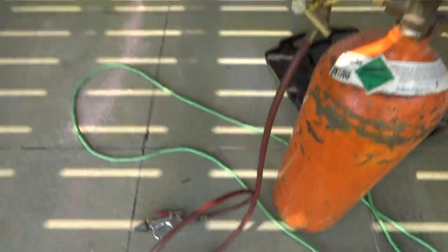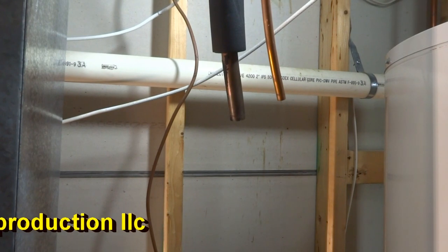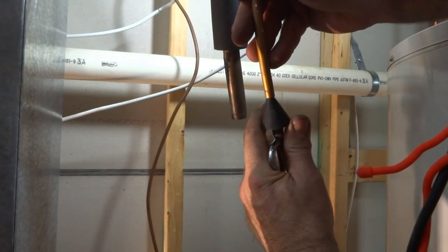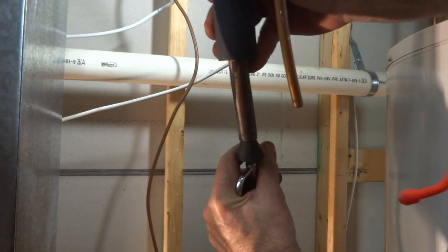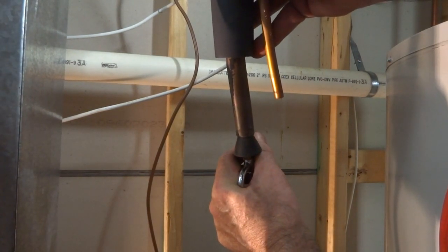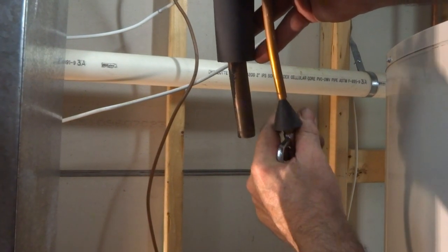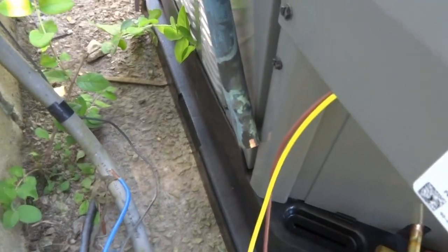So I got the refrigerant lines just dumping out here. I'm gonna blow them out with the nitrogen. Dry nitrogen and just blow them out. I don't see no dryer on the thing, so I don't see no filter dryer. A couple hundred pounds. See, nothing even come out. Thing was dry. Nothing even come out of it.